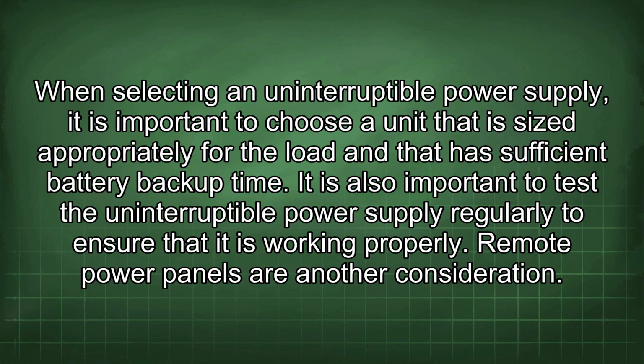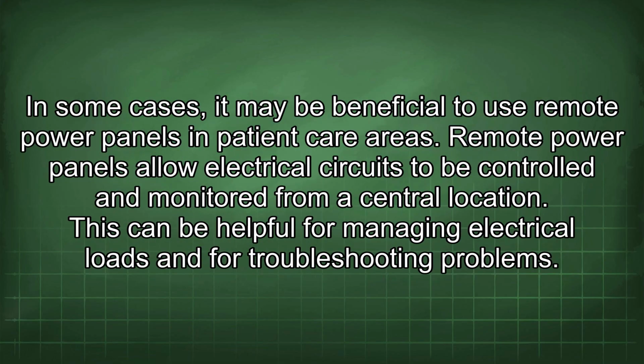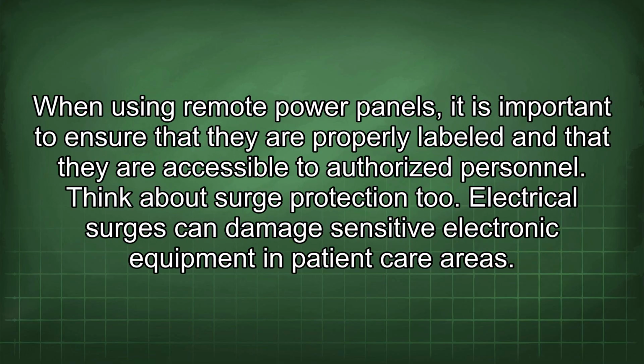Remote power panels are another consideration. In some cases, it may be beneficial to use remote power panels in patient care areas. Remote power panels allow electrical circuits to be controlled and monitored from a central location. This can be helpful for managing electrical loads and for troubleshooting problems. When using remote power panels, it is important to ensure that they are properly labeled and that they are accessible to authorized personnel. Think about surge protection too.